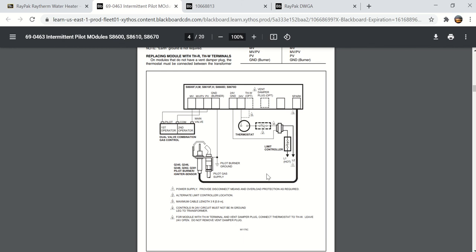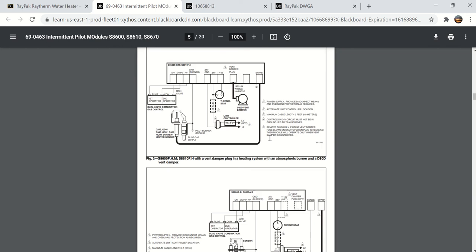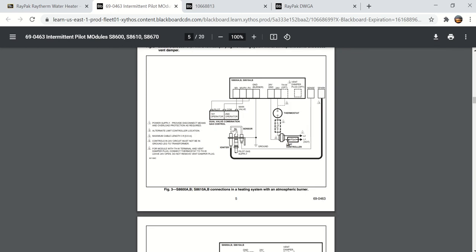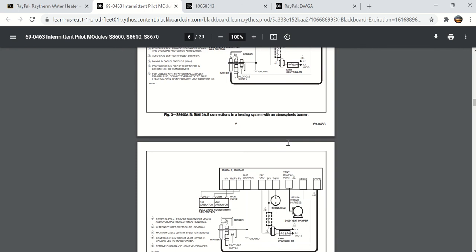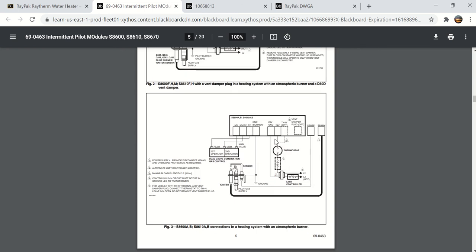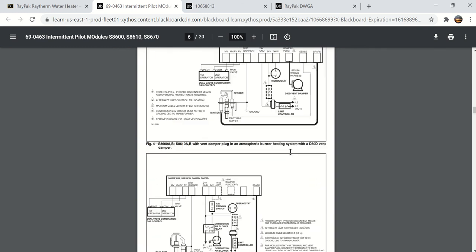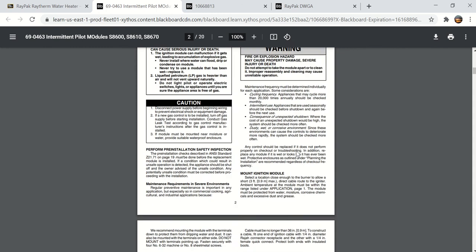This one uses a single spark. They do make models that have a vent damper plug. If you have a vent damper, which is a motorized damper on the flue gas vent, I never thought it was a real good idea, but they do it. Here's a model here that has a separate spark and sense. So you actually have a flame rod and an igniter. So there's different models of the Honeywell.